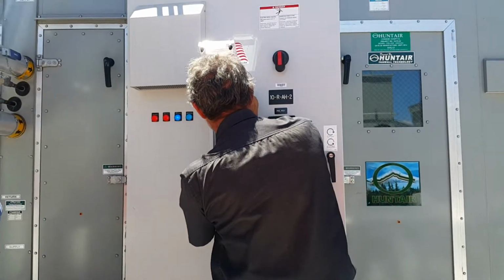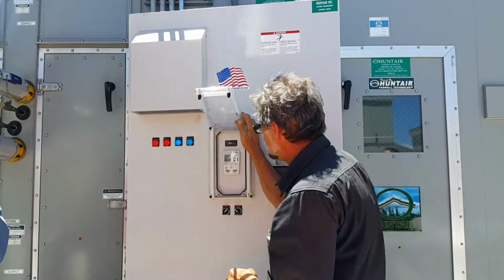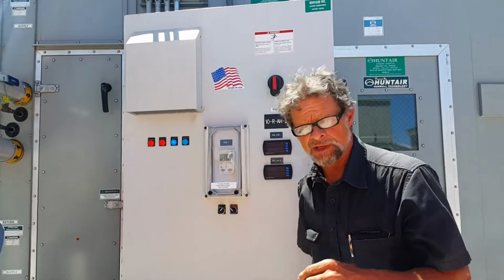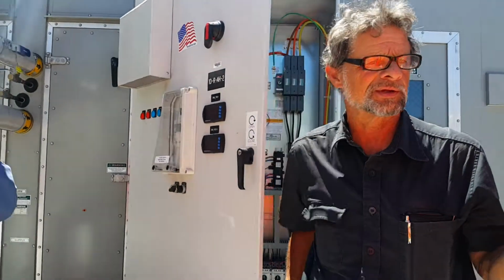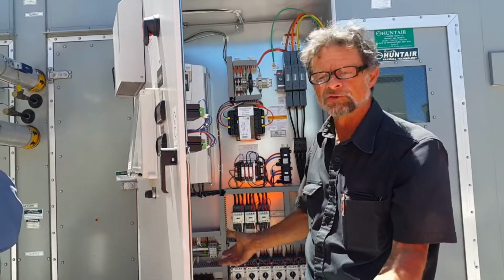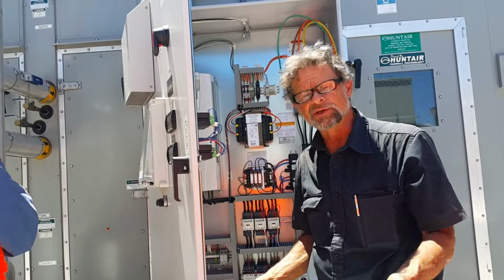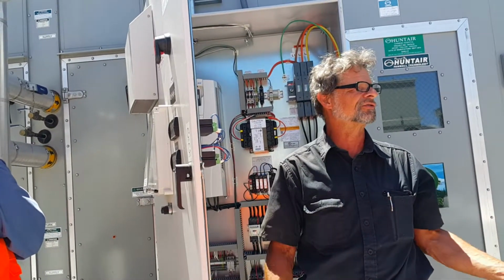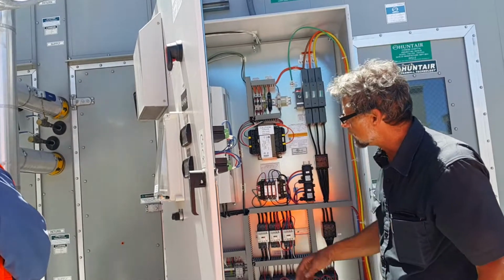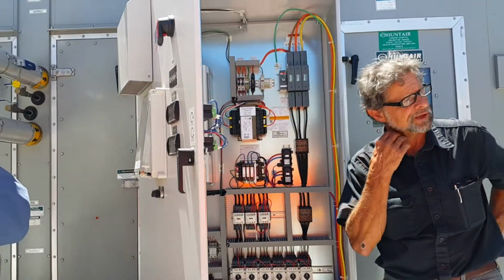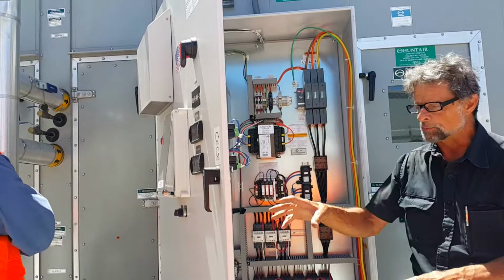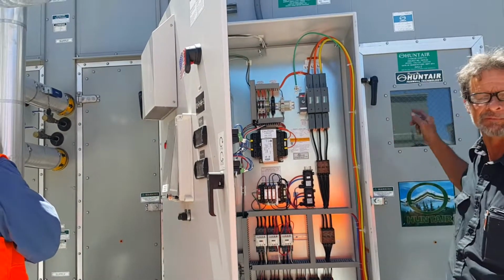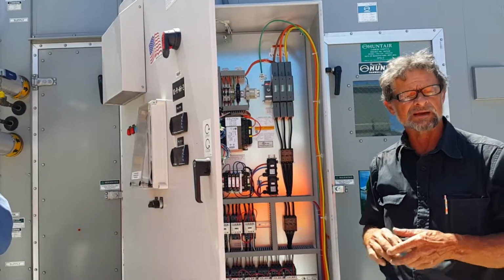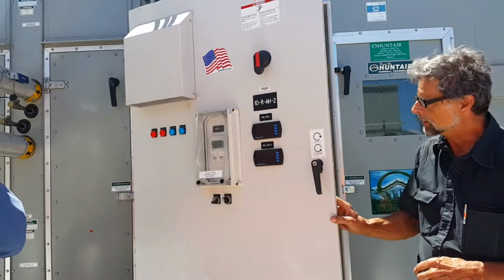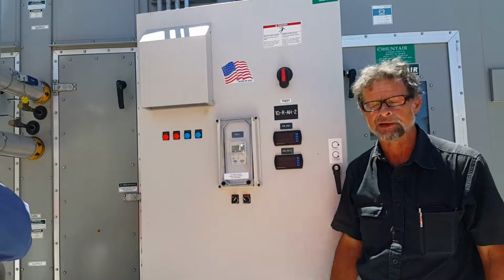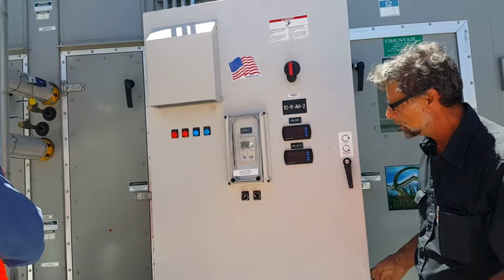Two billion settings. Yeah, that's the thing of it, these drives came out for industrial to begin with, 30 years ago. They have 1,000 parameters in them. For HVAC, you only need a dozen or so. There are some new units now coming out with an abbreviated drive and a separate panel that looks at all the drives for every motor, and they only have a few parameters. But you're right, you have to wade through 1,000 things to figure out what you do and don't need.